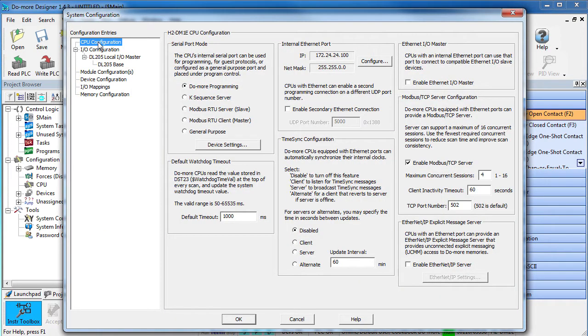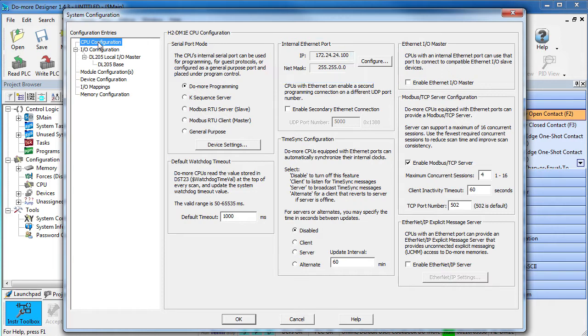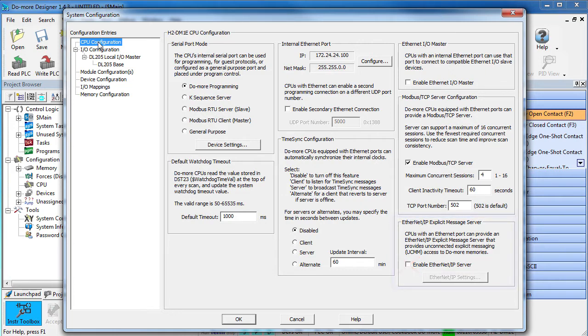Under CPU, we can make sure that the Do-more's IP address is on the same subnet as the imager. If not, we can change it here. And the Do-more in this example is the client controlling the imager, which is the server, so we don't need to enable the Do-more as an Ethernet IP server.